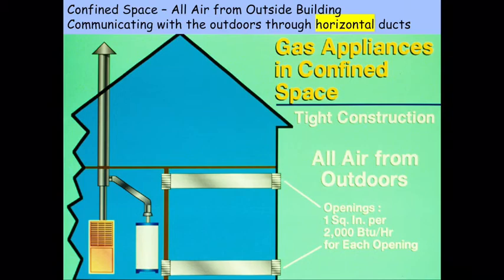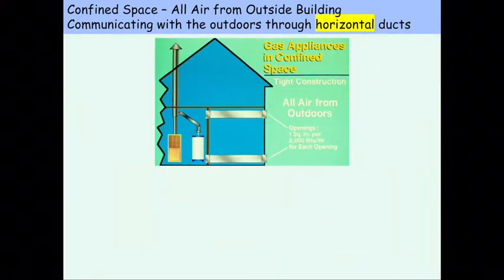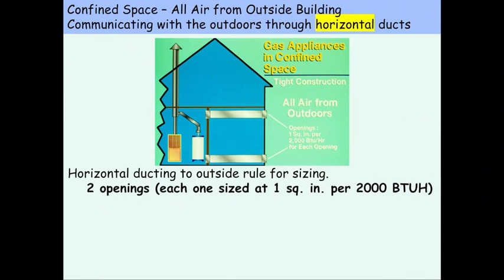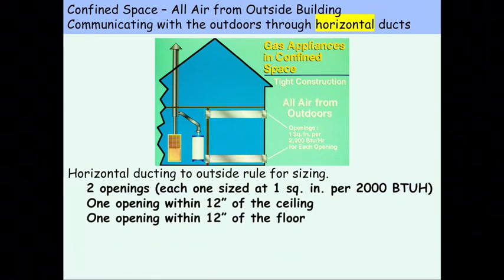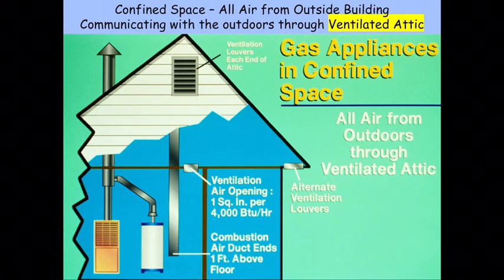Another option is using horizontal ducts to bring air from outside into a confined room. In this case, two horizontal ducts are run and each opening must be sized at one square inch per 2,000 BTUs per hour. The same placement rules apply: one within 12 inches of the ceiling, one within 12 inches of the floor, no less than 100 square inches, and no dampers — permanent openings only.